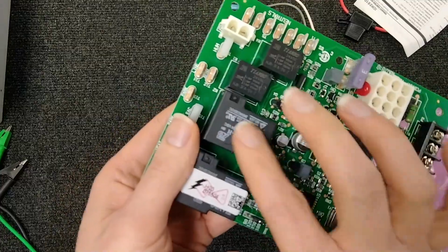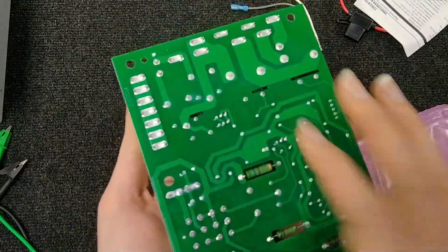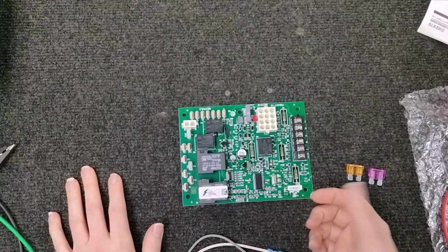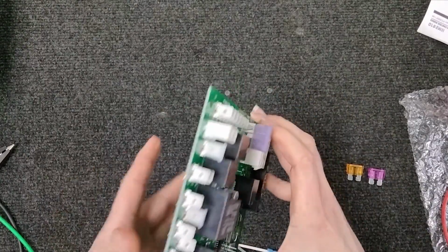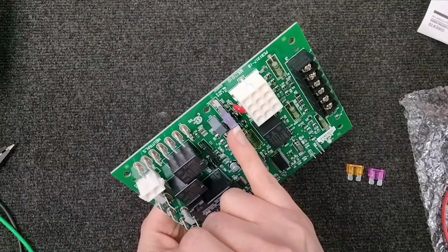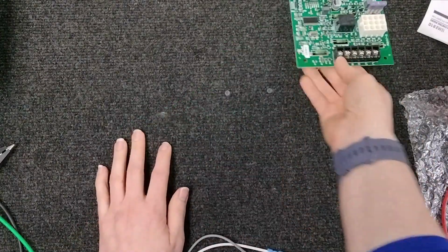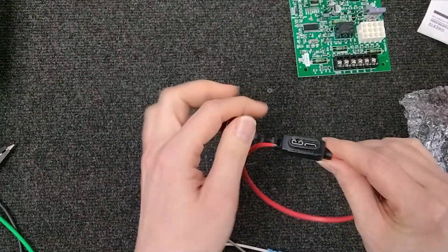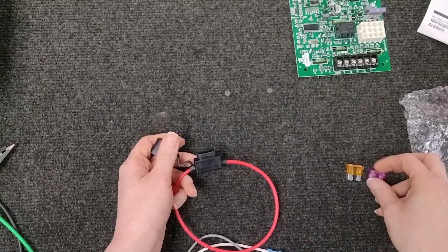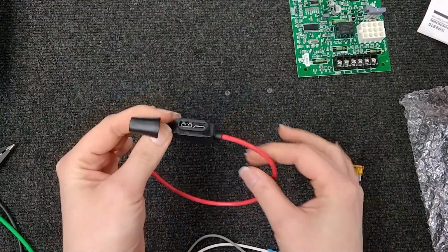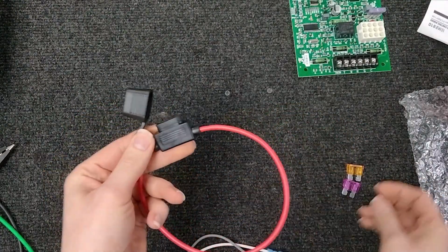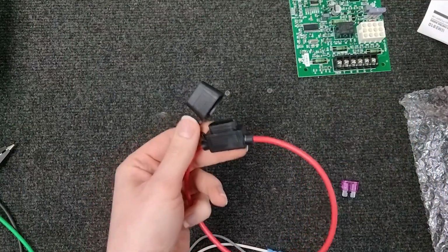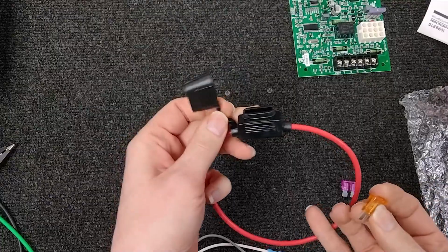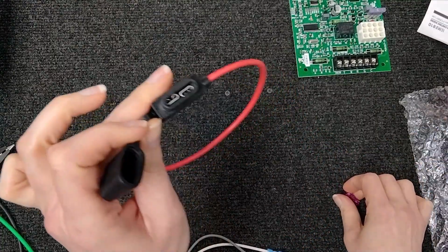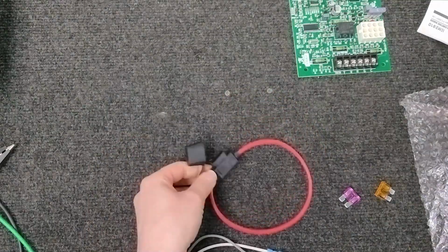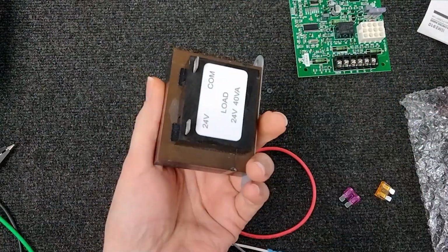Or that your relays have burned and it's very noticeable. Now, some of you might have old enough units that you actually do not have a fuse on your control board. A lot of times, if a technician comes out to work on a unit, they can put one of these inline fuse holders in there, which are really great to have to catch any low voltage shorts. I'd recommend putting one of these that would go from your transformer on your 24 volt side.